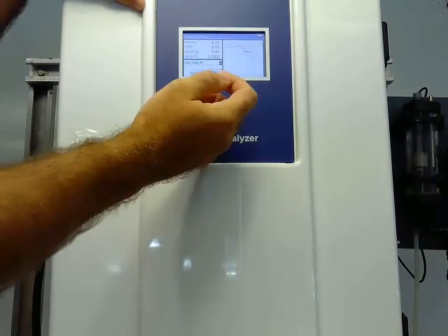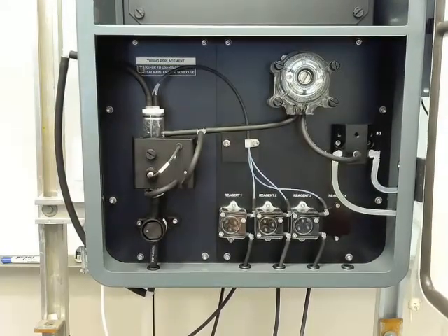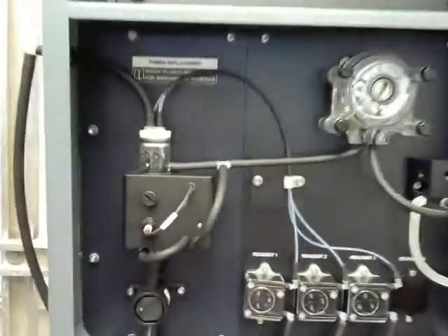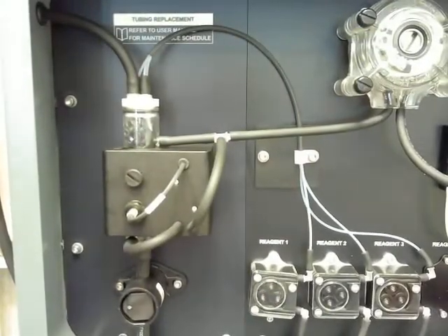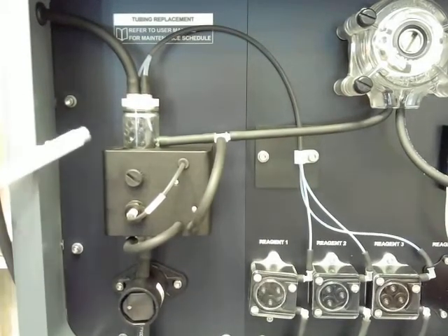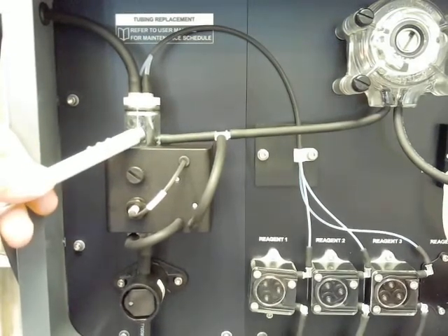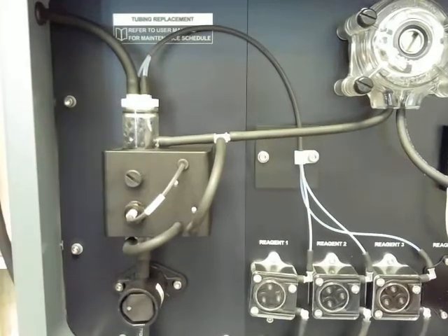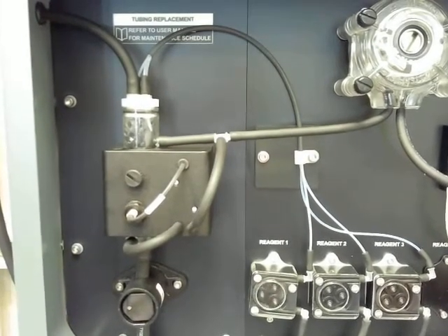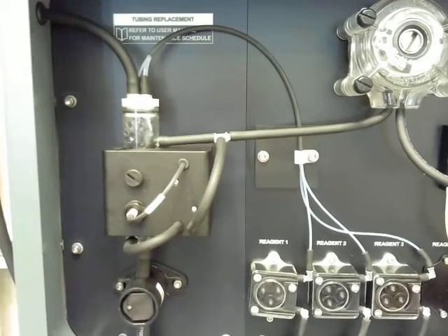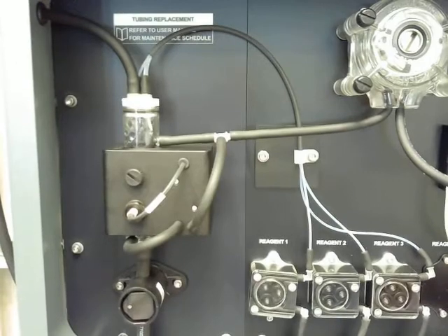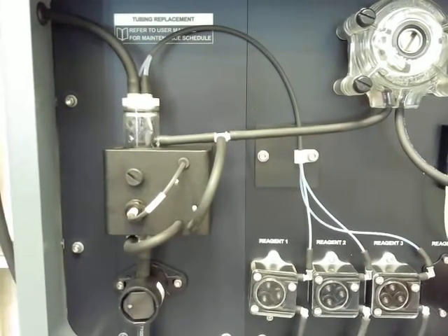Once we select that, change our timing to 60 seconds, and press on. You should hear our reagent pump start to activate. Once the pump is turning and drawing in our reagent, we're looking for reagent at this flow cell cap to start dropping into our flow cell. That's just an indication that we've got our reagent primed and we're ready to go. There it is. A 60-second time is enough to not only flush out anything that might be in there, but to make sure we get our reagent from the top to the bottom of our tube.